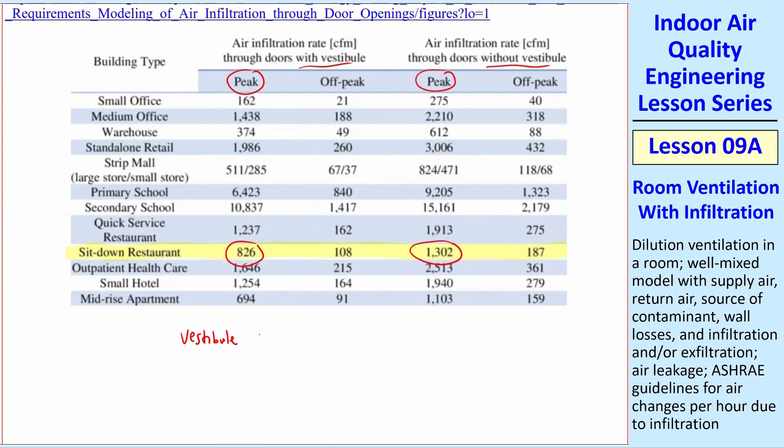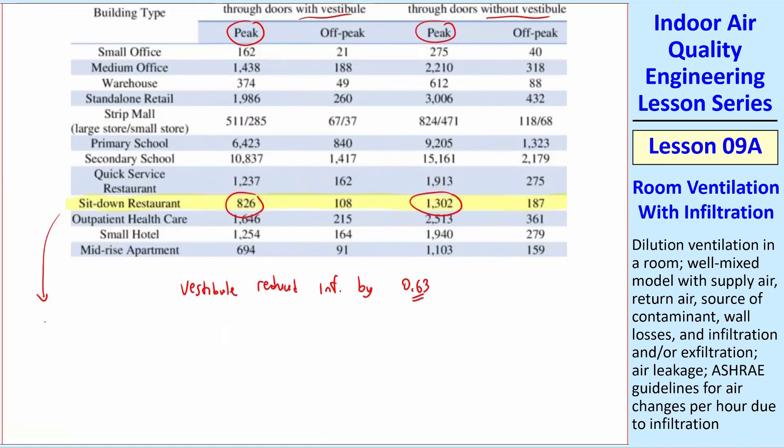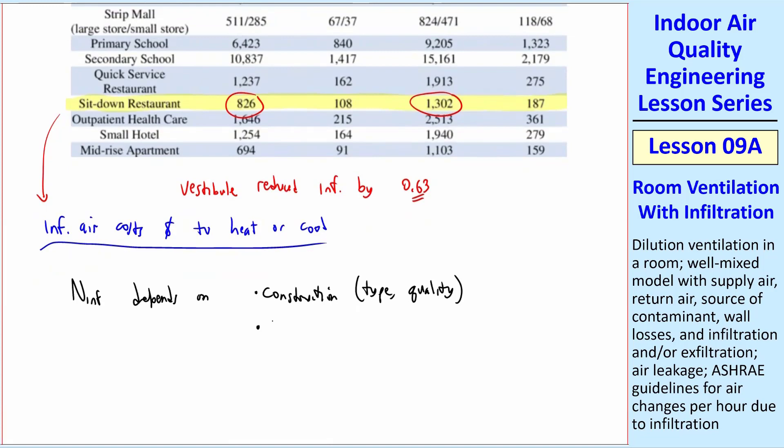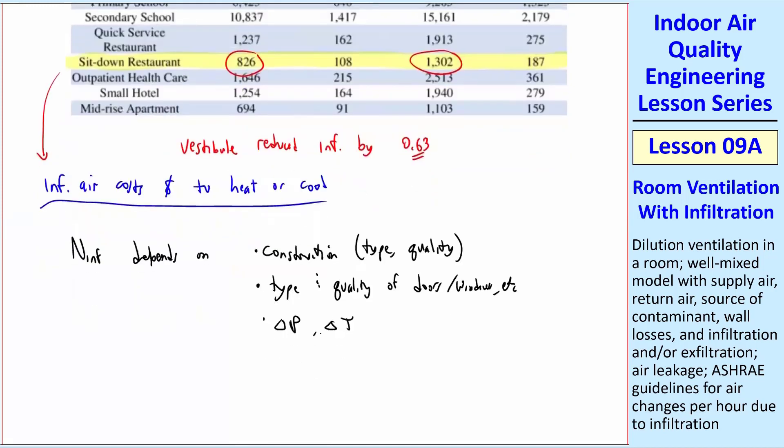Every infiltrated air costs money to heat or cool, depending on if it's winter or summer. And so you want to try to avoid infiltration. The bottom line is that N infiltration depends on the construction, not just the type of construction, but the quality of construction, the type and quality of the doors themselves, doors, windows, along with Delta P, Delta T, as we just talked about, and a whole bunch of other things.